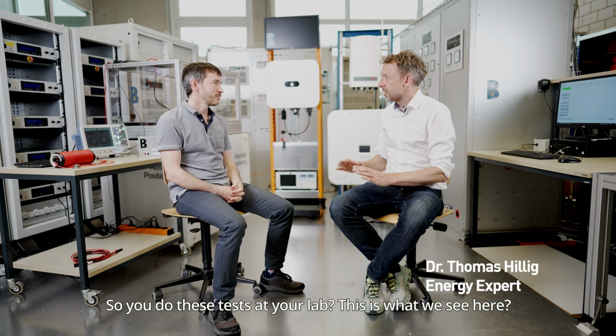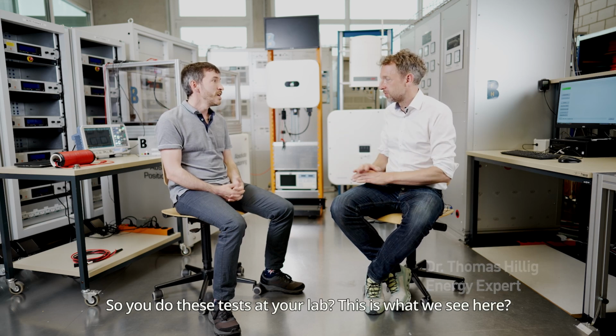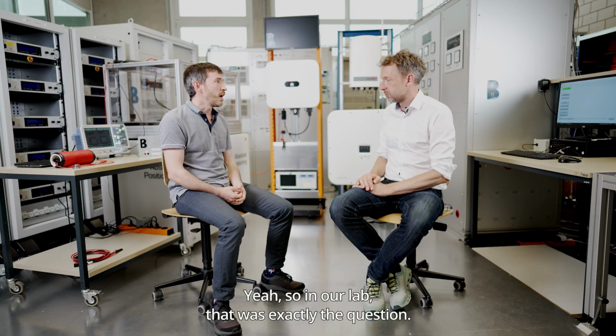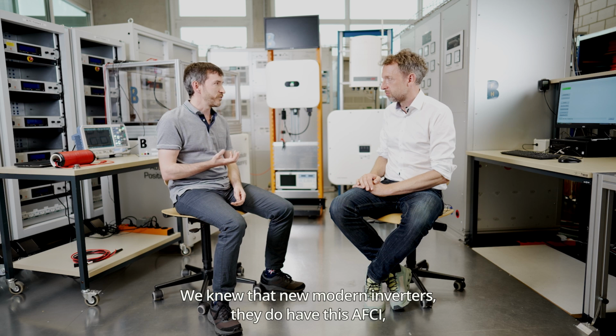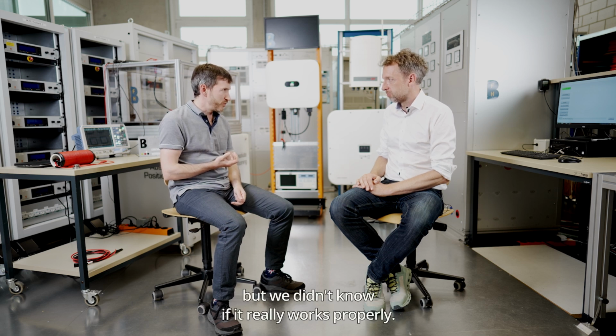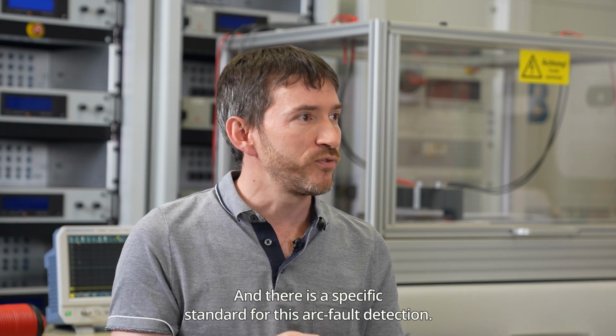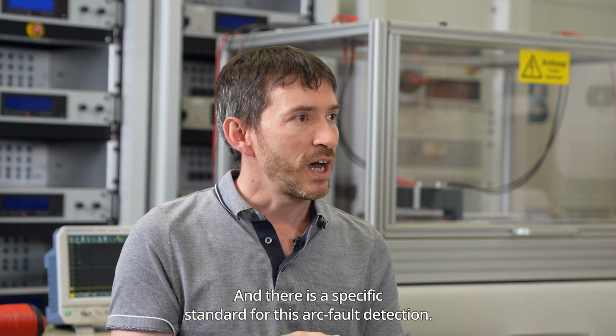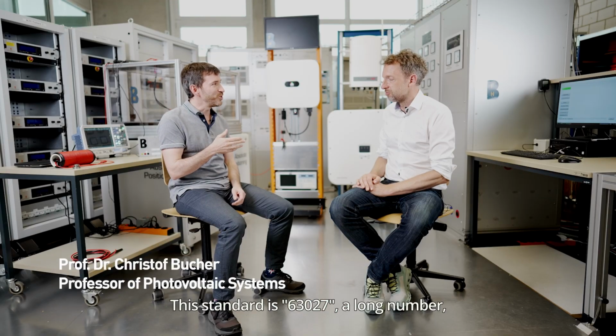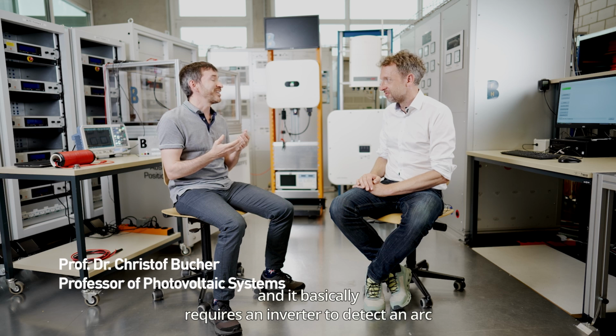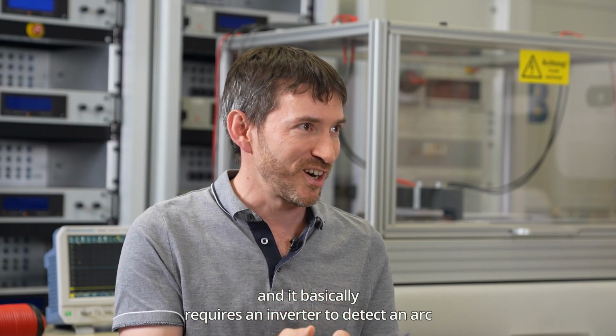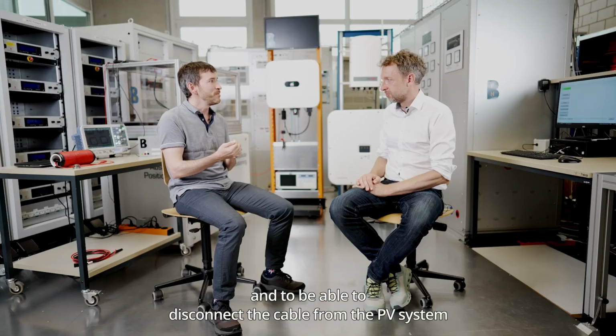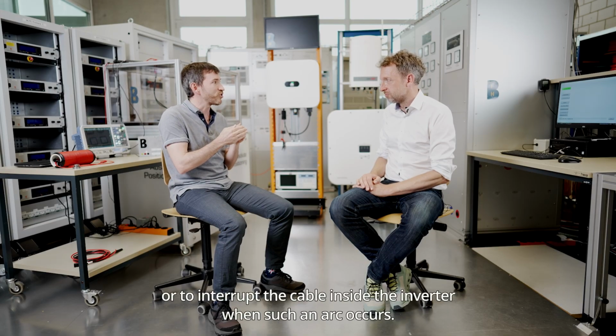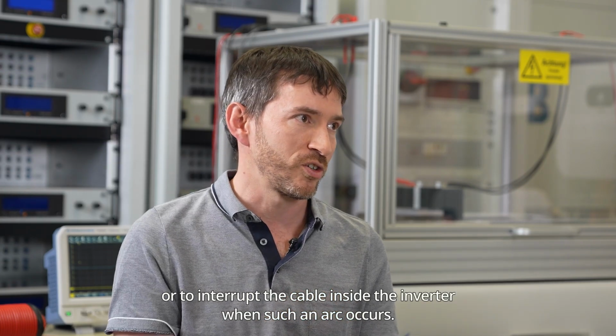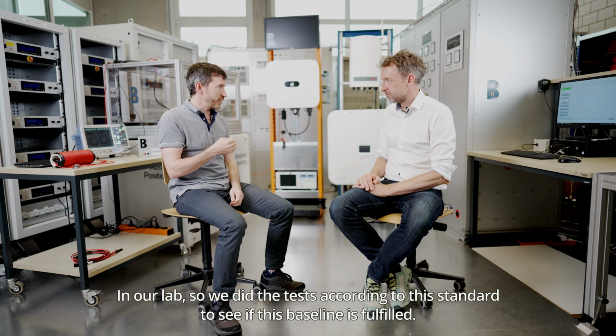So you do these tests at your lab. This is what we see here. Yes, that was exactly the question. We knew that modern inverters have this AFCI, but we didn't know if it really works properly. There is a specific standard for arc fault detection, 63027, which requires an inverter to detect an arc and to disconnect the cable from the PV system, or to interrupt the cable inside the inverter when such an arc occurs. In our lab, we did the tests according to this standard to see if this baseline is fulfilled.